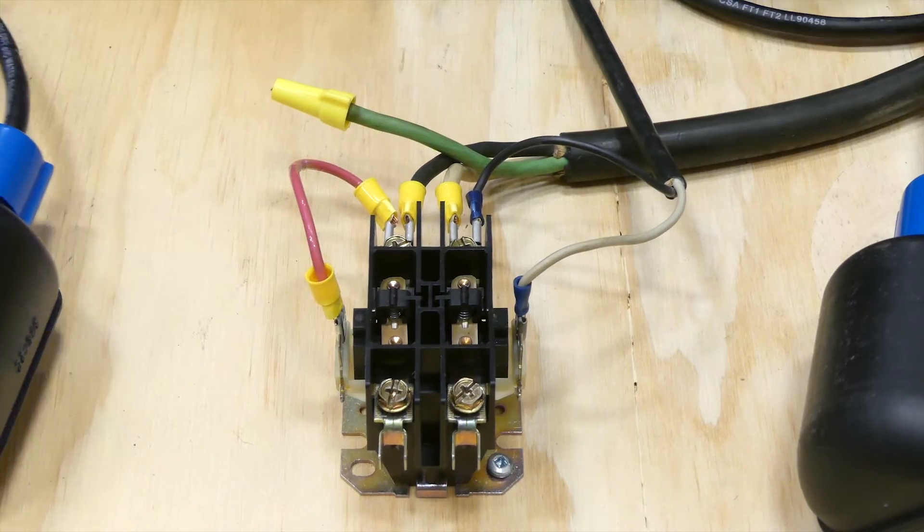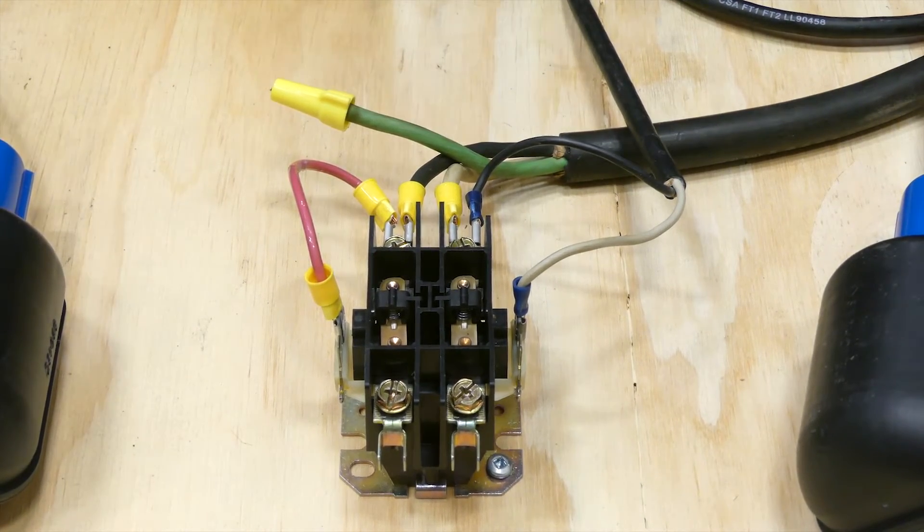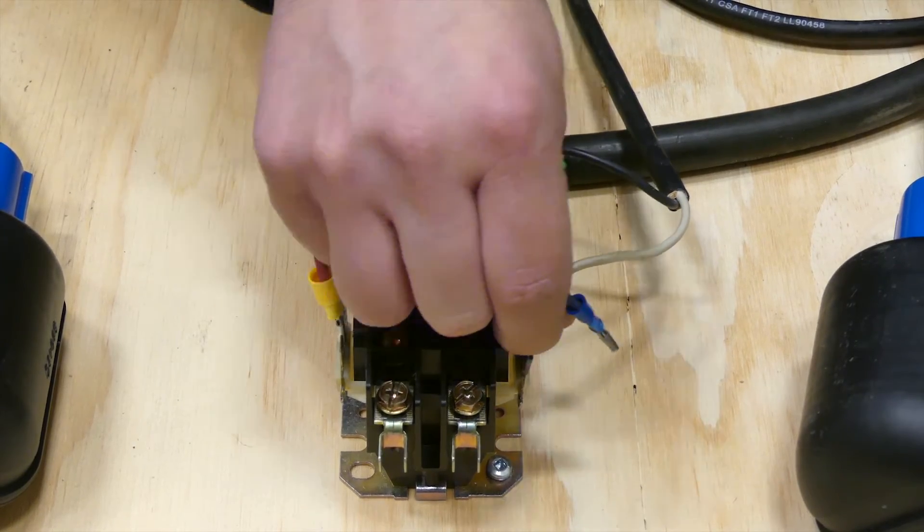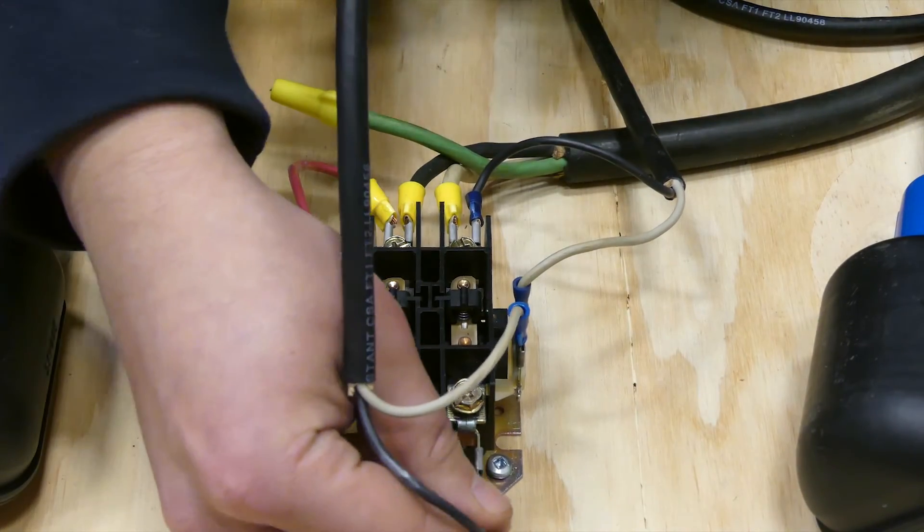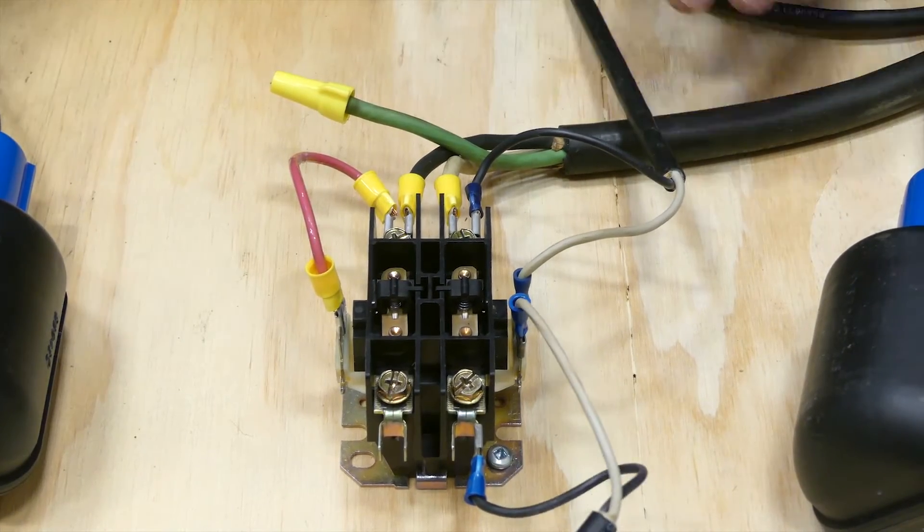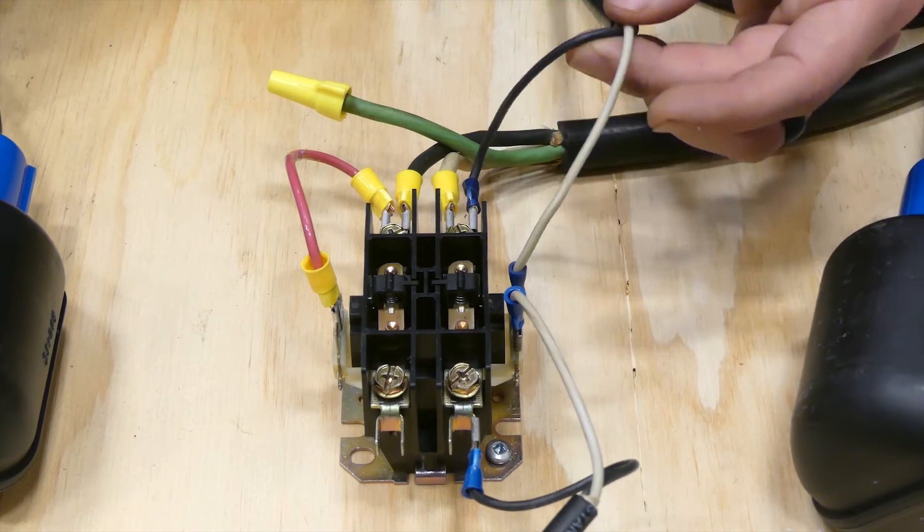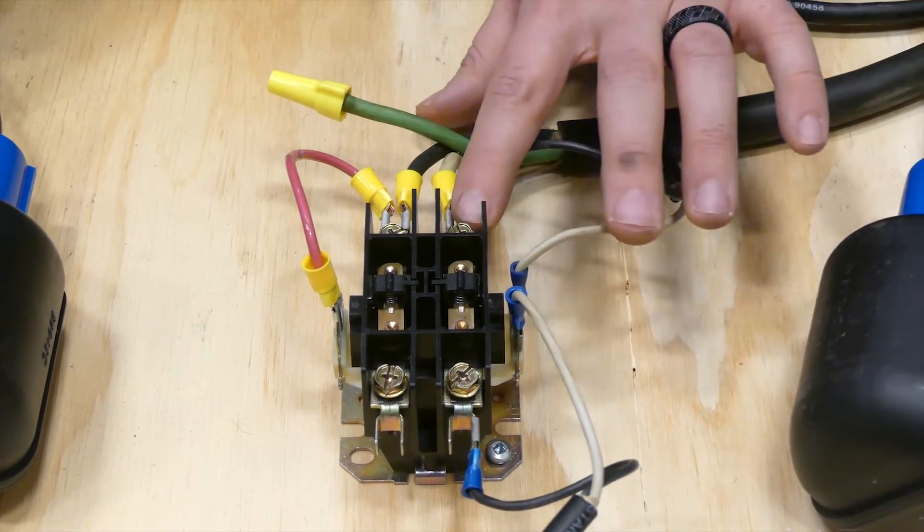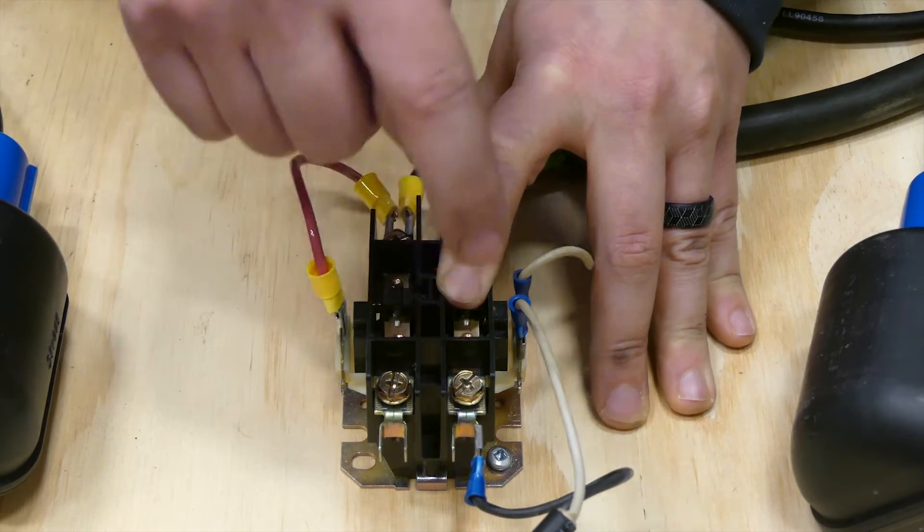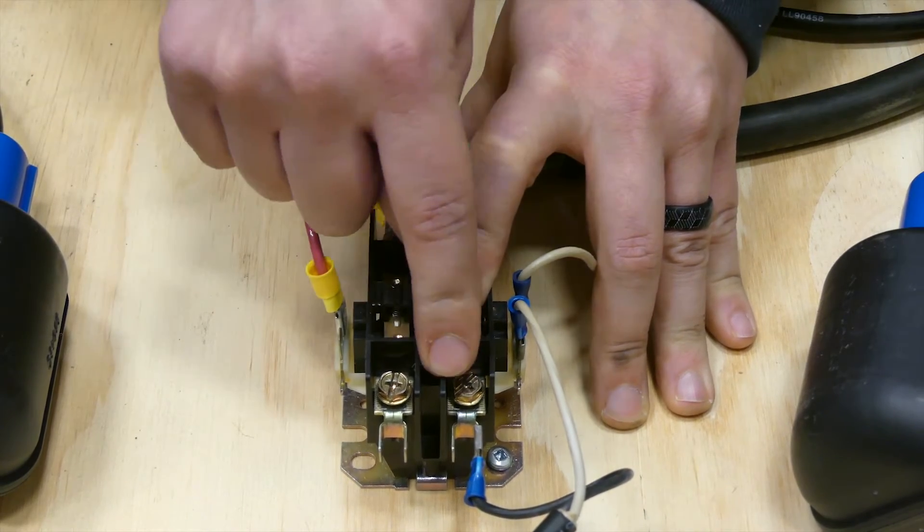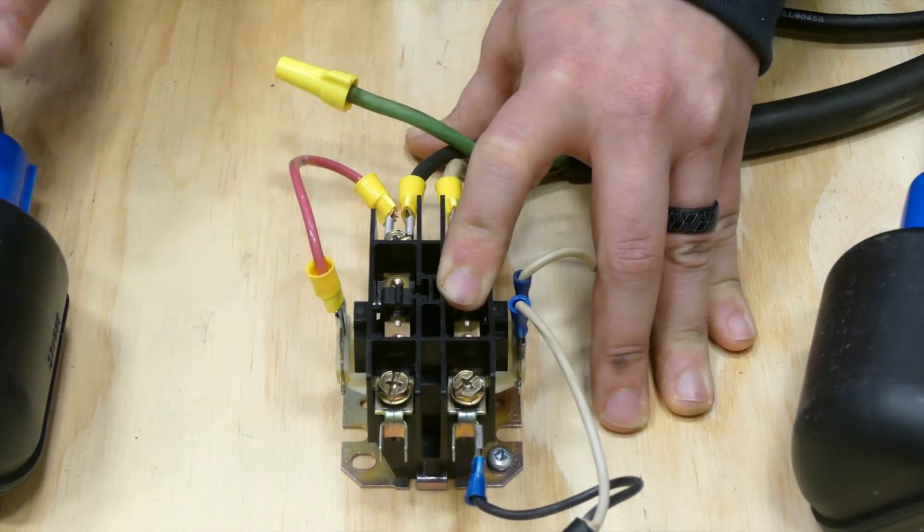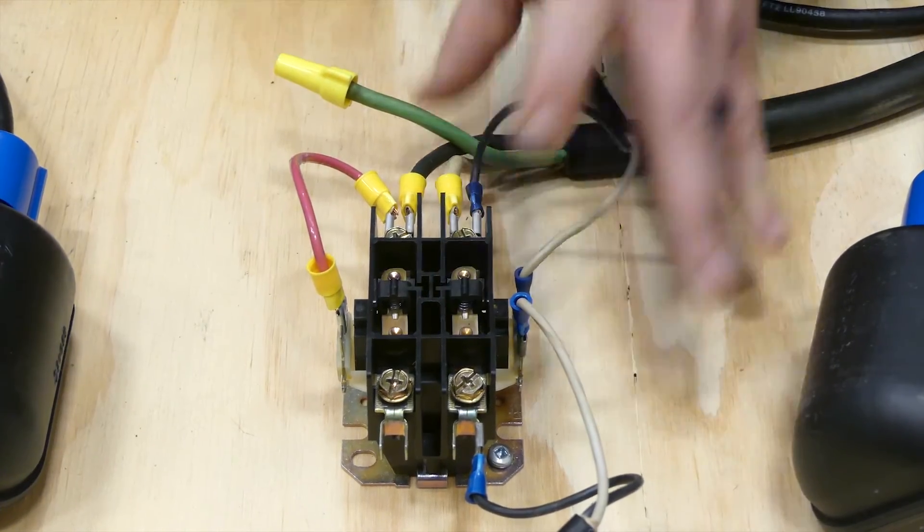Where things get a little bit different is the second float switch is going to be located just like this. What's going to happen is when this float switch closes the contactor initially, the power will be coming down through this part of the coil. So this float switch will then be able to send voltage to the coil until this switch opens up. Let's show you that in action real quick.